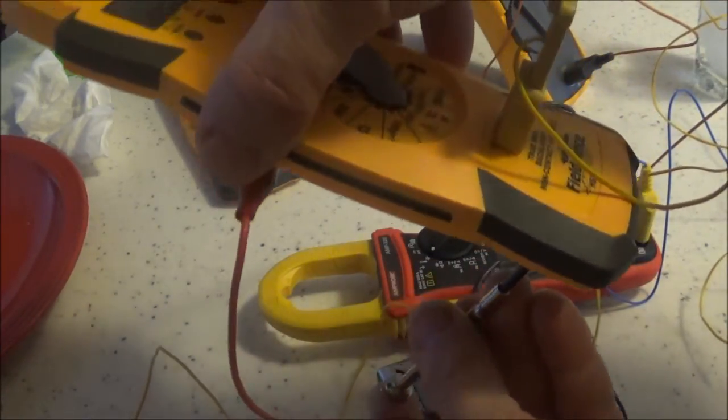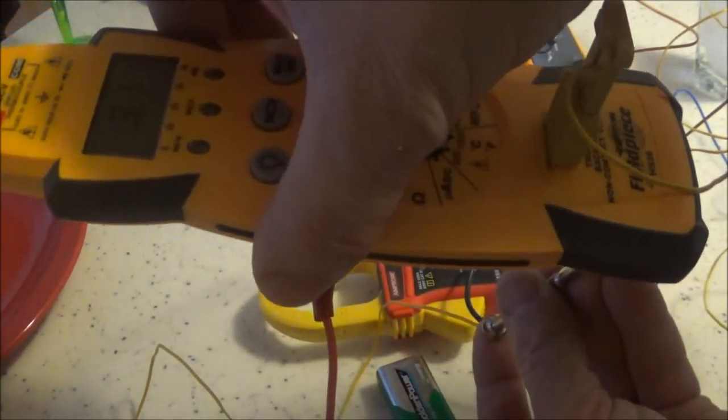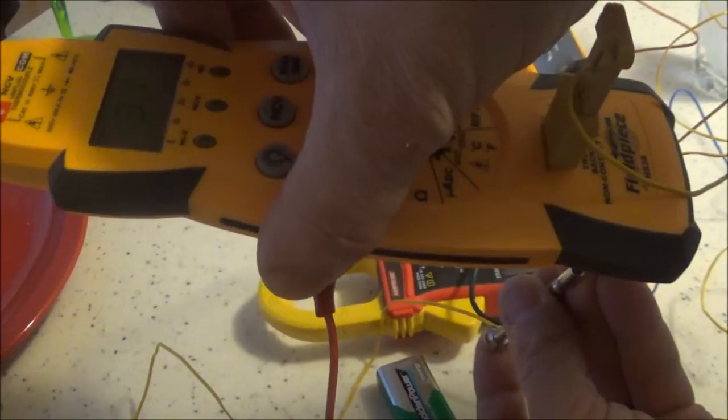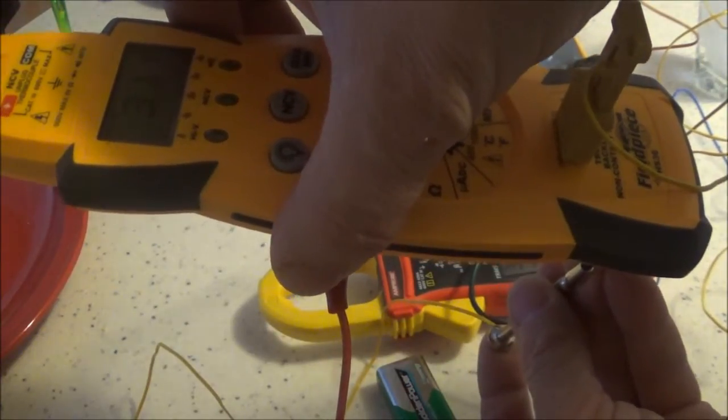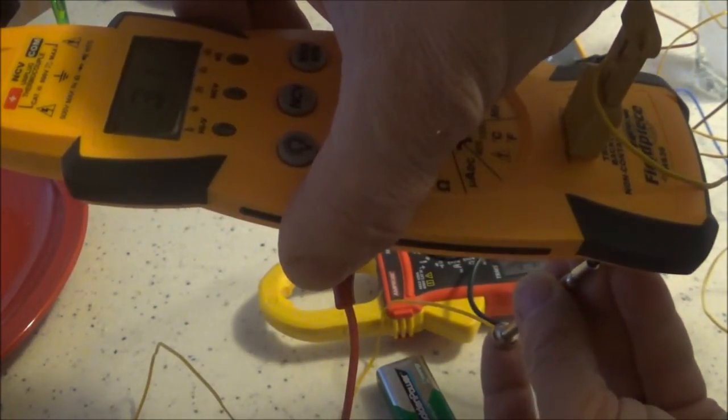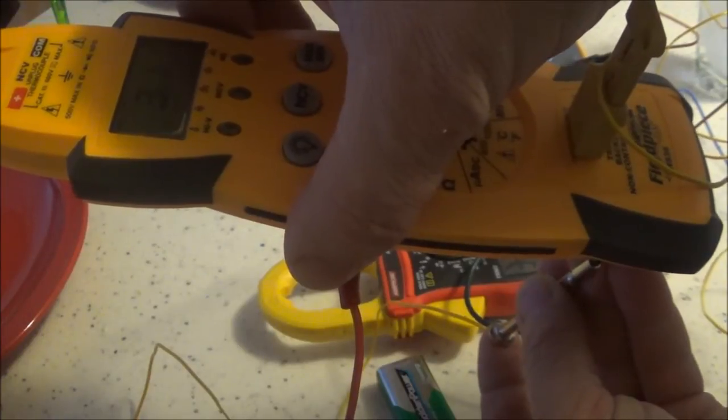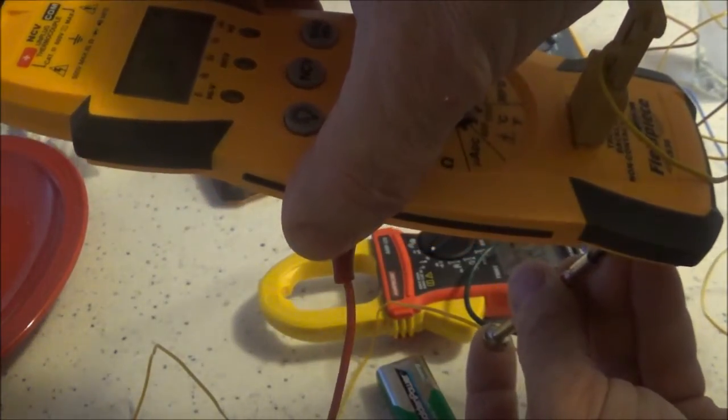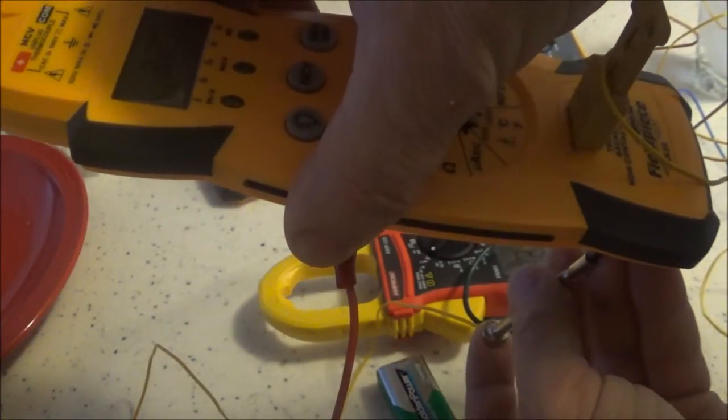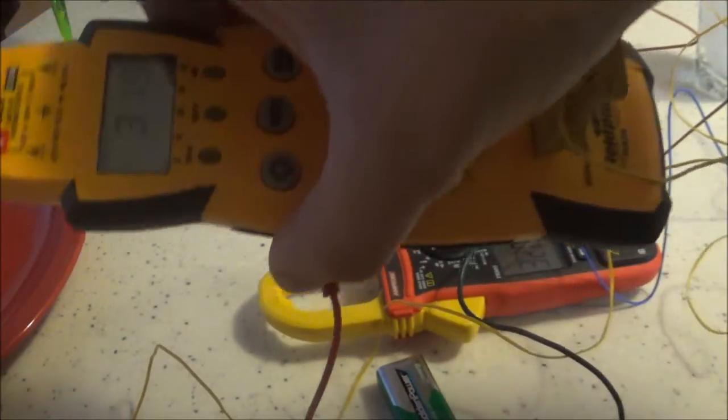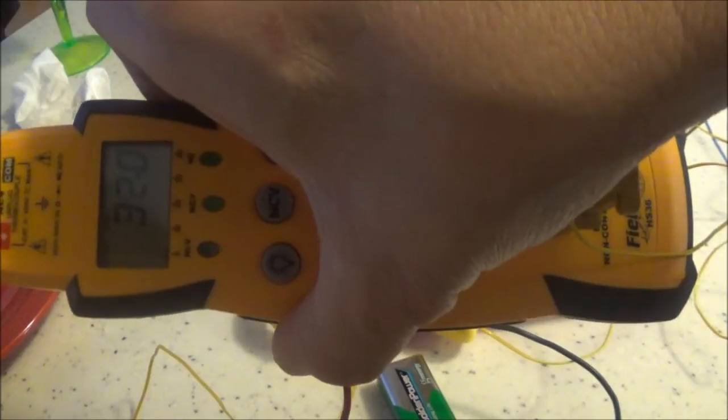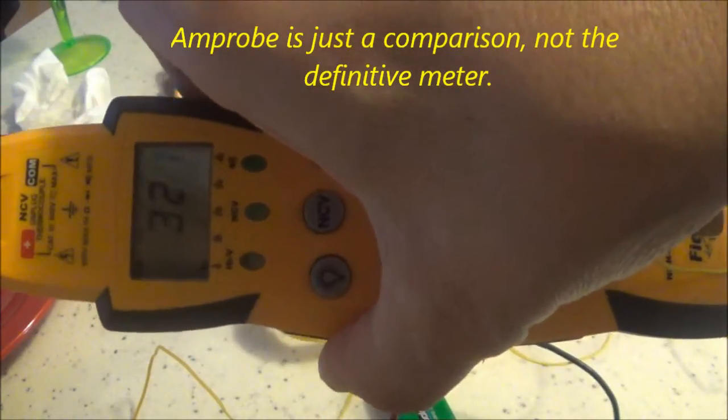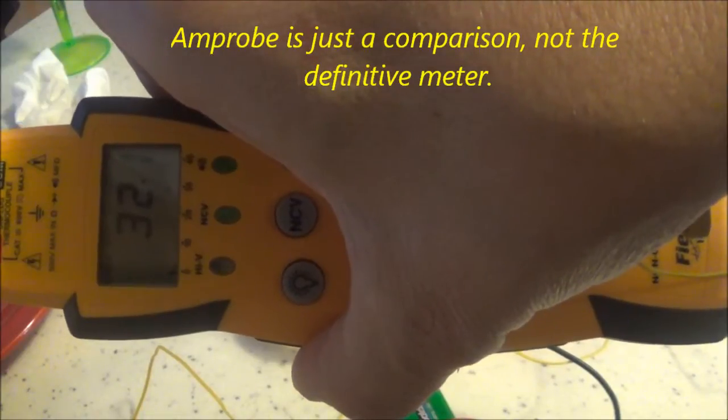So I'm going to adjust that. Turn it clockwise. There we go. Look at that. Turn it just a hair. And that's reading exactly what the Amprobe is reading. So now I feel I'm calibrated.